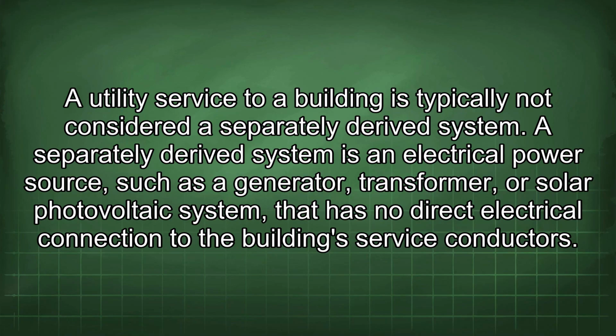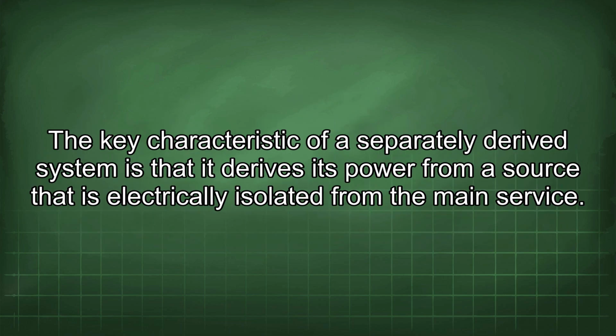Utility service to a building is typically not considered a separately derived system. A separately derived system is an electrical power source, such as a generator, transformer, or solar photovoltaic system that has no direct electrical connection to the building's service conductors. The key characteristic of a separately derived system is that it derives its power from a source that is electrically isolated from the main service.